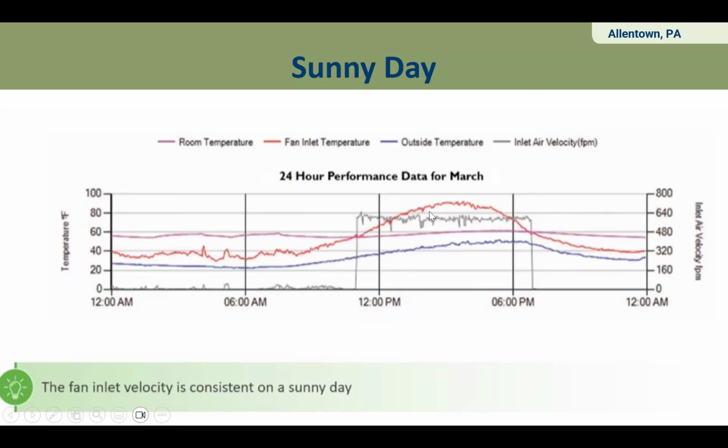You can see dips in the red corresponding with the fan activity shutting on and off. And then at, probably what, 6:30, 7 o'clock, it turns off again. So this is just indicative of how you can monitor and assess the viability of the product. And you can see that delta between the red and the blue line grows throughout the day. And that, right there, is roughly at the peak, that 50-degree temperature delta.